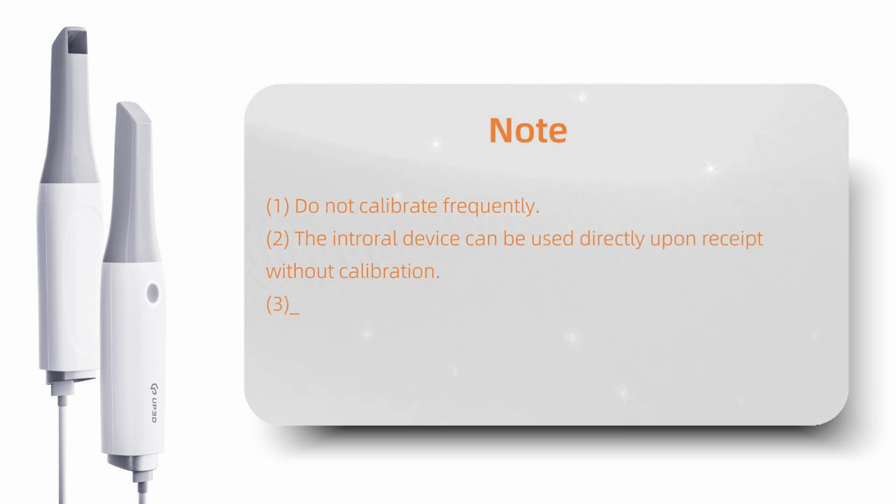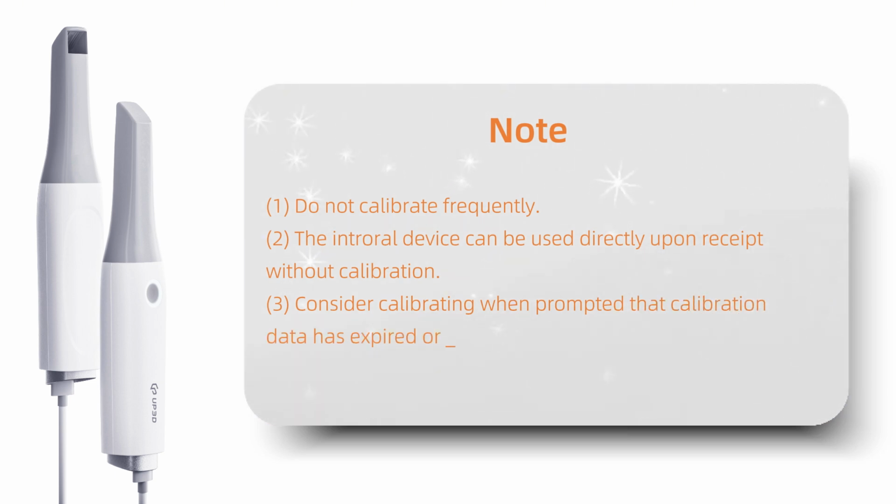Do not calibrate frequently. Two, the intraoral device can be used directly upon receipt without calibration. Three, consider calibrating when prompted that calibration data has expired or when device accuracy issues arise.